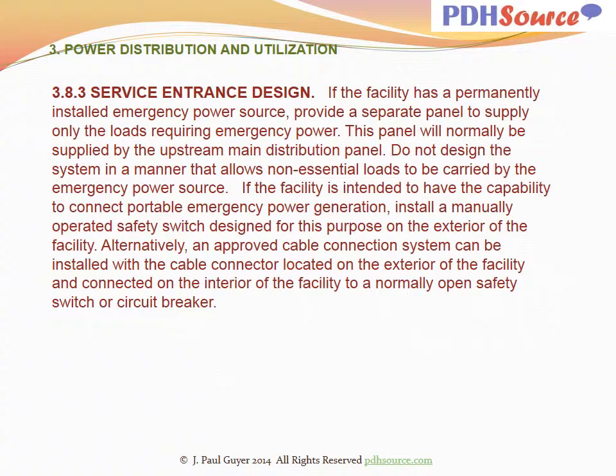If the facility is intended to have the capability to connect portable emergency power generation, install a manually operated safety switch designed for this purpose on the exterior of the facility. Alternatively, an approved cable connection system can be installed with the cable connector located on the exterior of the facility and connected on the interior of the facility to a normally open safety switch or circuit breaker.